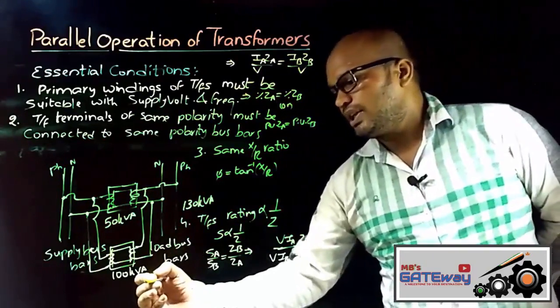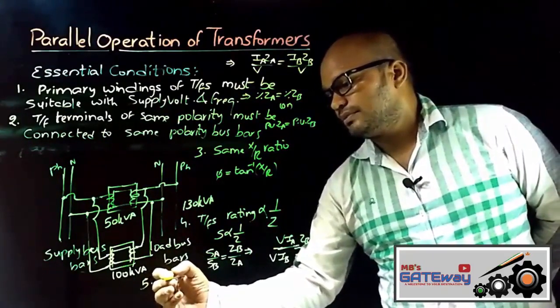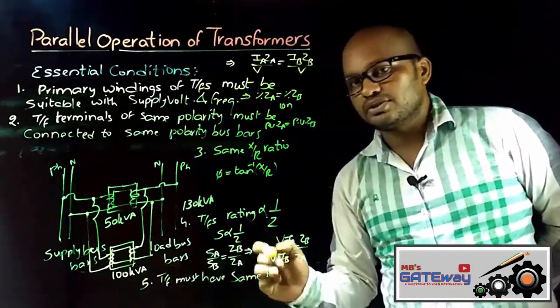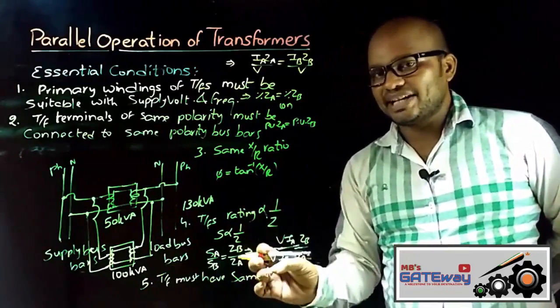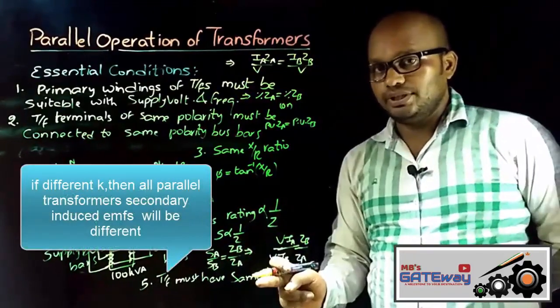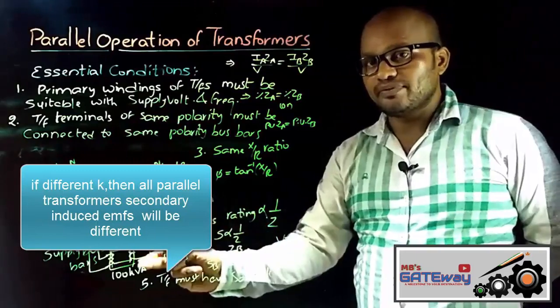And the fifth important condition is that transformers must have the same turns ratio, which is also called the same transformation ratio constant K, which will indicate that the transformer induced EMFs must be the same.